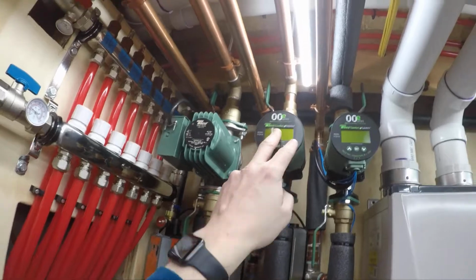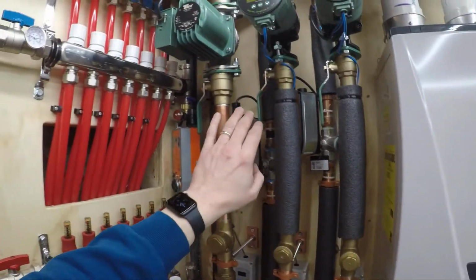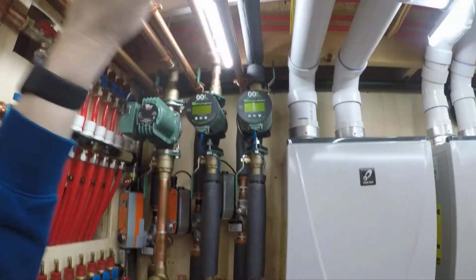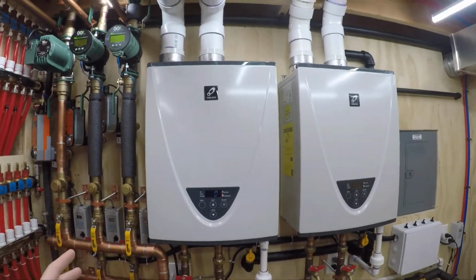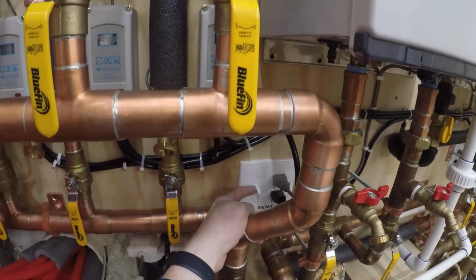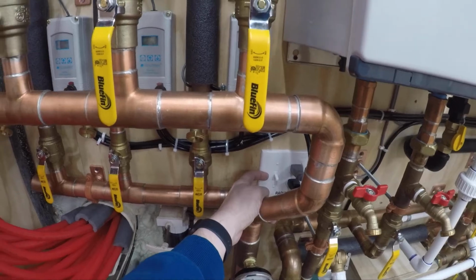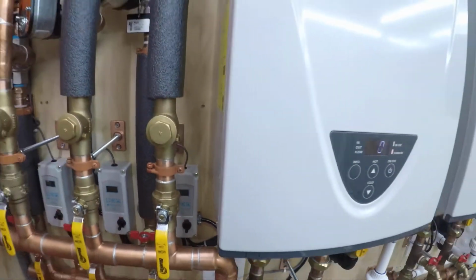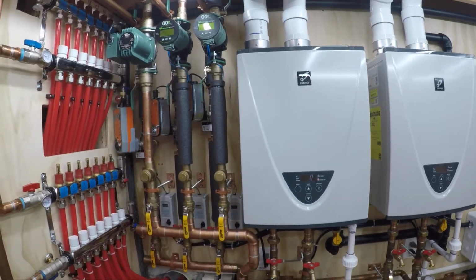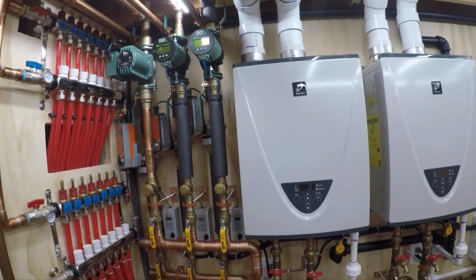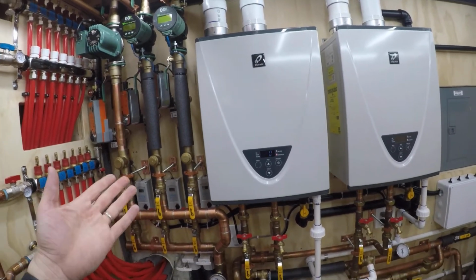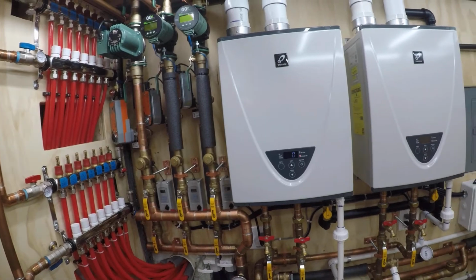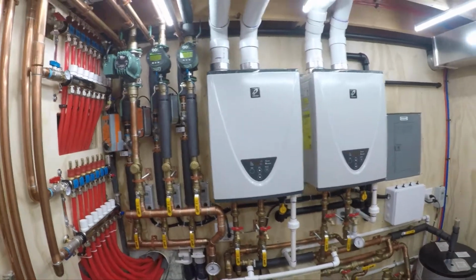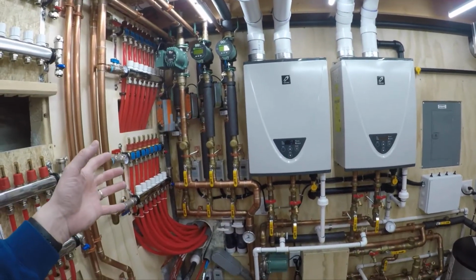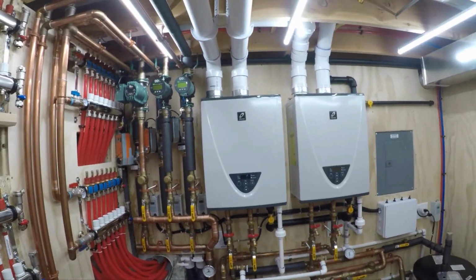Same exact thing for the slabs here. Same setup, same aquastat setup, same three-way valve setup, pump setup, everything. So whenever I turn on this radiant switch right here, which can be controlled from my smartphone, which the radiant one is not so much that important. The radiant one basically, you know, you turn it on in the fall, and typically you leave it on, you know, if you want the floors warm. Now I have it off now so that I can talk and I don't have to talk over everything. But yeah, basically, you know, I leave it on, it does all of this, and it's good to go. Like, you don't mess with it.